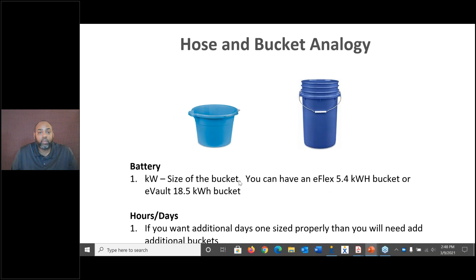Now, how does that relate to the design principles? Well, the more water, more flow, the more buckets. The more water, the more buckets. So when we go to the minimum sizing chart that we have, keep this in mind. And this goes to respecting the inverter output. So if you have 50 amps of inverter capacity, and that inverter capacity relates to an 8 kW inverter, well, if you want to have 100 amps of ampacity, that means you need 2 inverters, which means you need more buckets. So when we go to the minimum sizing guide, we'll use that 2-hour design principle that I had mentioned before.